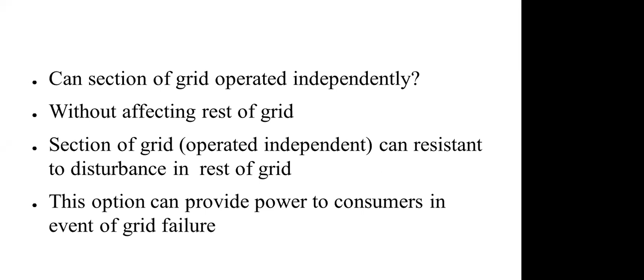That is nothing but islanding. If that is possible, then it is possible to have a microgrid. If these two points are satisfied, in my view, you can provide power to a particular section of the grid in case of grid failure, whether it's a fault in the grid or usual maintenance—anything can cause it.